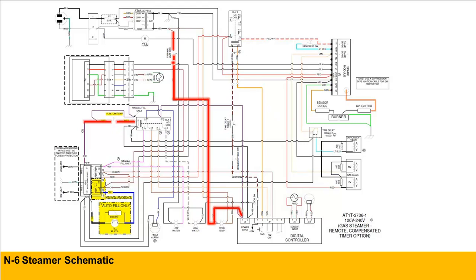As far as testing the high limit switch, that's easily bypassed. All you have to do is take the switch out of circuit and jump across. Now, once again, this is for testing purposes only. We never leave a high limit or any safety bypassed. So if you bypass that switch, using a jumper or just reconnecting the wires, and everything turns on, at that point we know we have a bad switch.